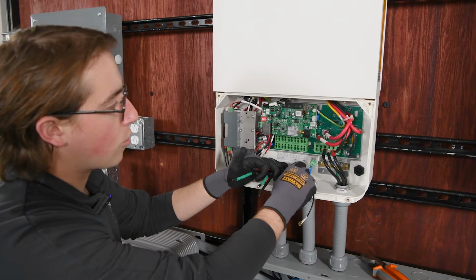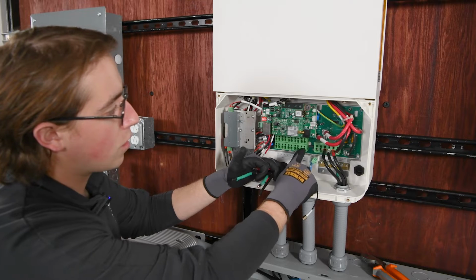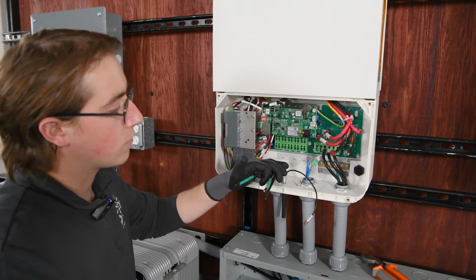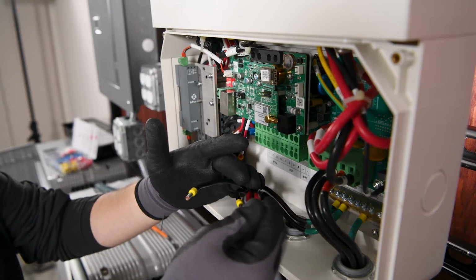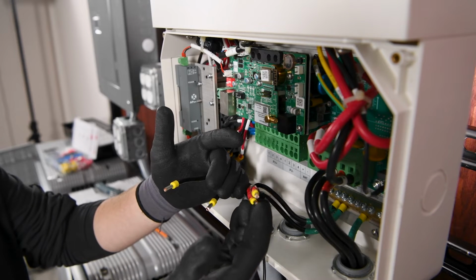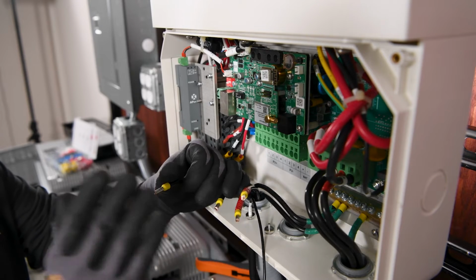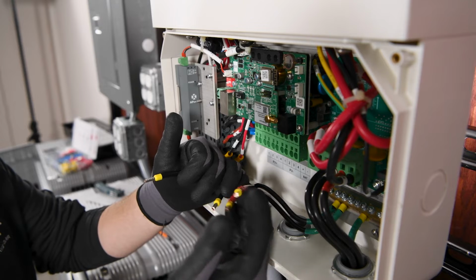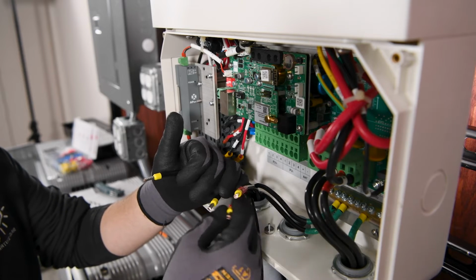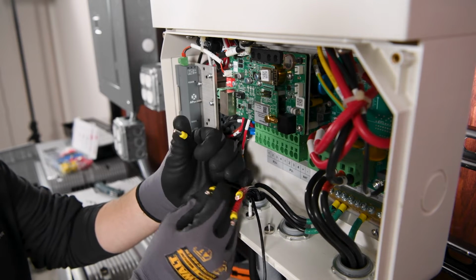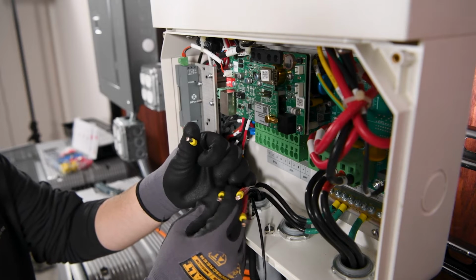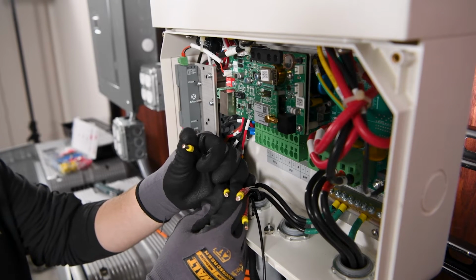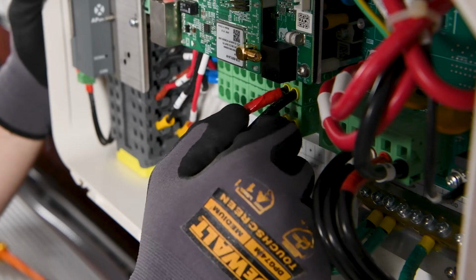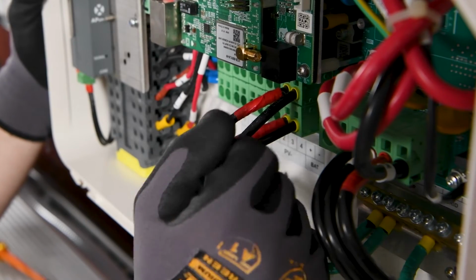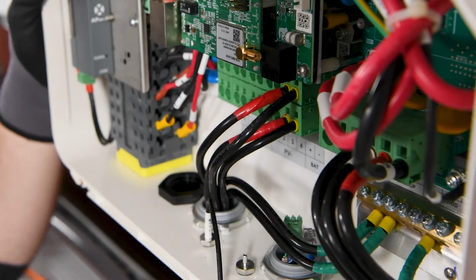So we'll take our primary and secondary battery and connect it to the top and bottom battery positive and negative terminal blocks here. Here we have all of our battery conductors, or all of our battery cables, ferruled. Now, remember, these are not connected to the battery currently. These are not live conductors. We're going to make sure that we connect our power sources, like our battery and our grid and our PV, at the very end. Next, we'll connect these battery conductors, these battery power cables, to our terminal block.